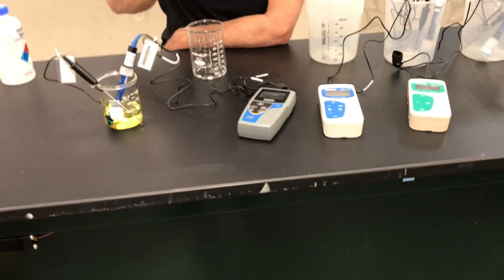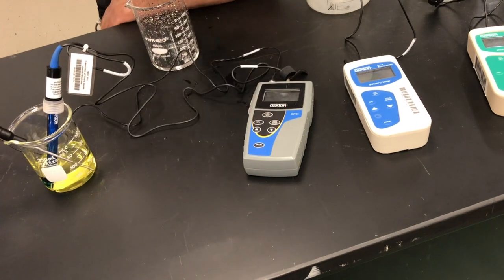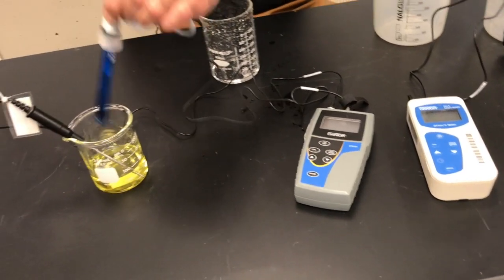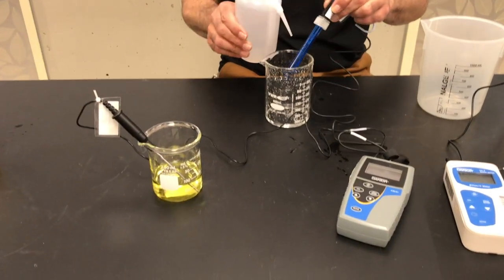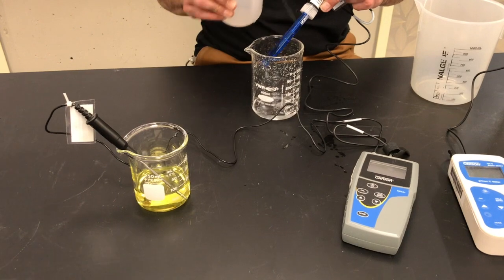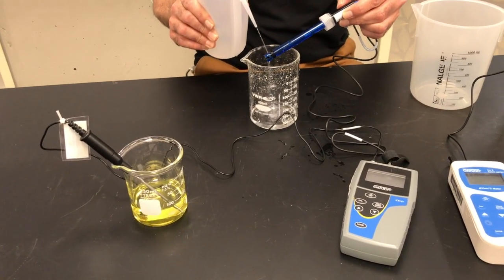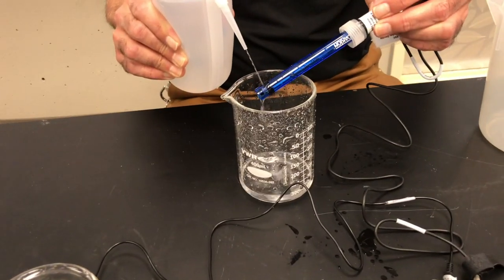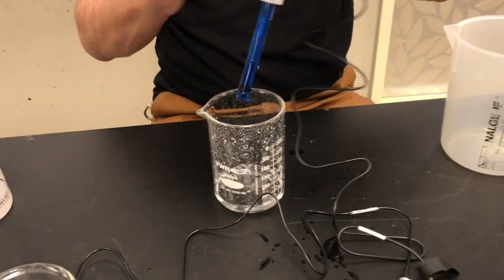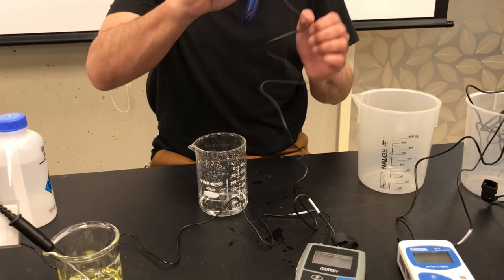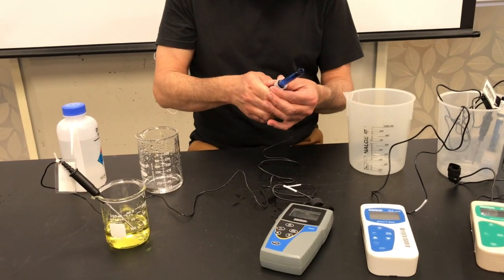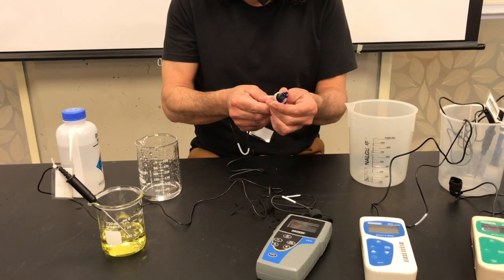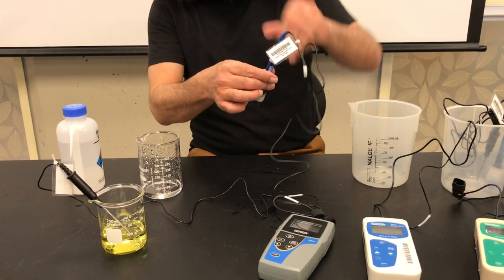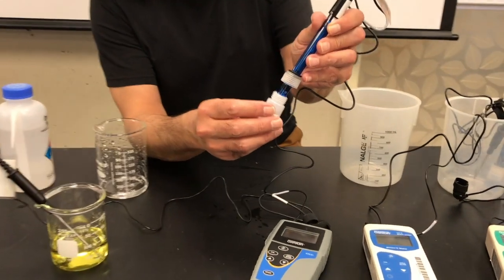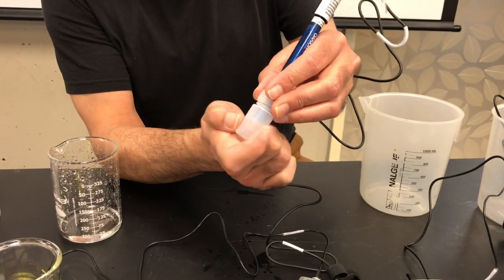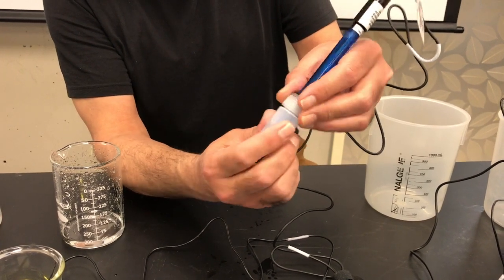When you're finished, you just turn it off, press the off button, and then you go backwards. Take the probe out and rinse it with water. I tend to concentrate the rinsing on the glass membrane and the junctions. Then we shake off as much as we can and carefully push the cap closer to the tip. Then we put the bottle back in, and just like before, don't turn on the probe, just turn the bottle till it's closed.